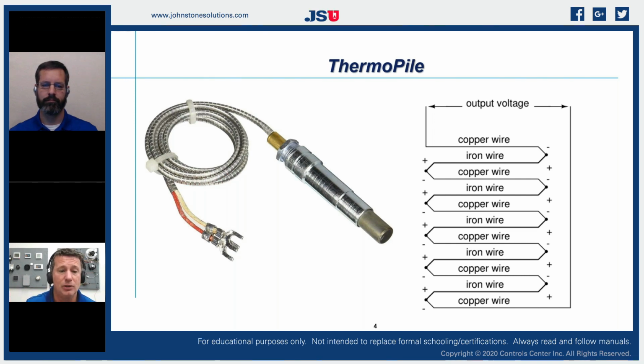Because if we think about electrical, if we put something in a parallel circuit, we're going to maintain our pressure, we're just going to increase our current. If we put that in a series circuit, we're going to increase our pressure, our voltage. So if we needed more voltage to hold in our solenoid, say we had a larger solenoid that needed more power to hold it, it needed a larger magnetic field, we simply increase the voltage by adding more thermocouples together. And then we would put them in one housing, and we called it a thermopile or a power pile generator. And we use that technology forever.